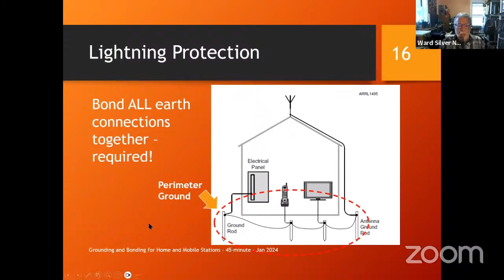The other thing we talked about was don't create paths for lightning through your station. Here's a typical example: here's the tower outside, and lightning comes, either hitting the tower or nearby, and you get a big lightning surge. Here comes the current surge down the tower, and it says, oh, here comes some feed lines, I'm going to follow them. Here's my nice entry panel, connected to a ground rod, so some of the current's going to go there.